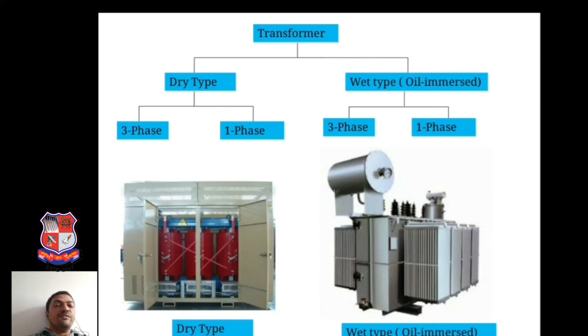Single phase and three phase dry type and wet type transformers are available. The first picture shows a dry type transformer, a panel type or cabin type, where no insulating oil is used. In the second picture we show a wet type or oil immersed transformer. Oil is used as an insulating material and also as a cooling medium. It is circulated through the main tank, radiators and conservator tank.